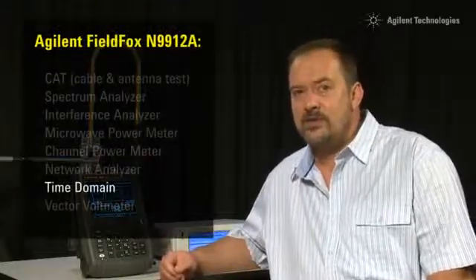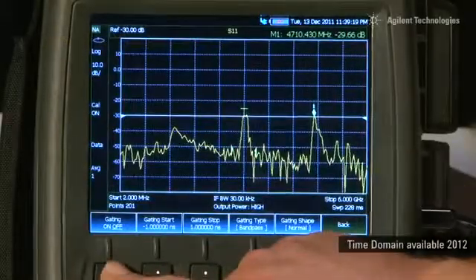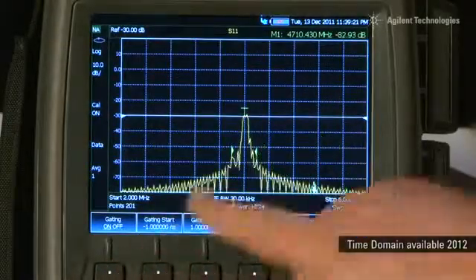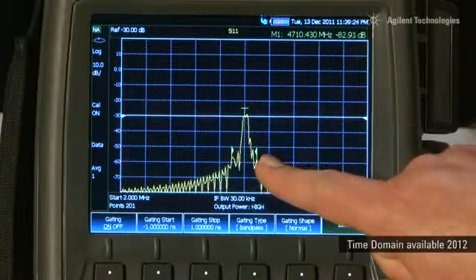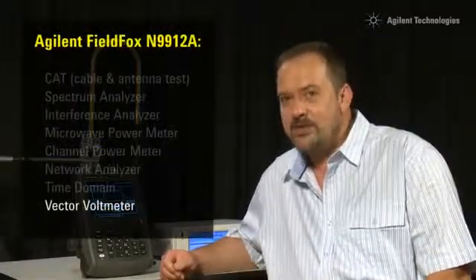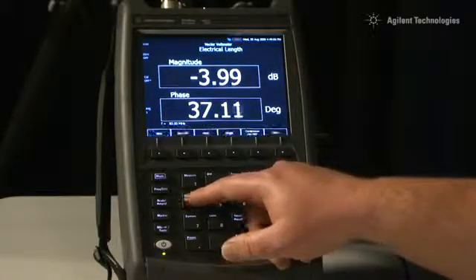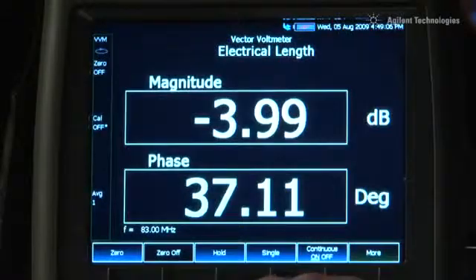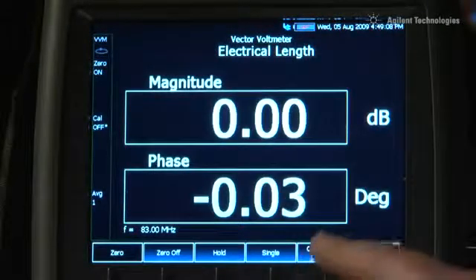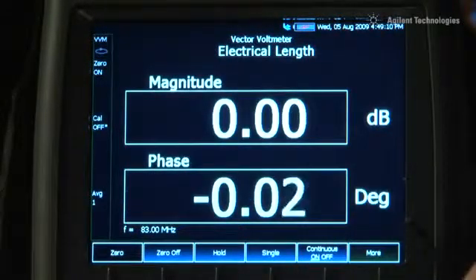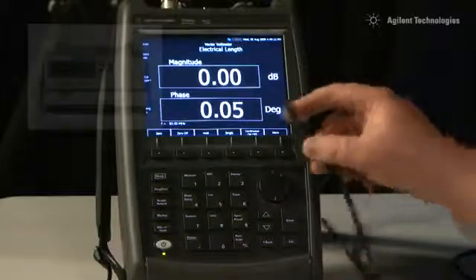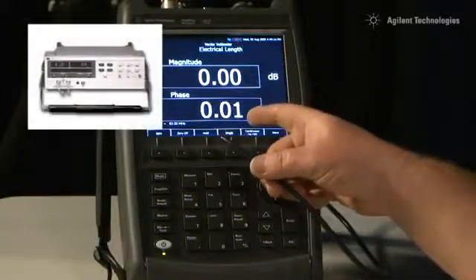And with the new time domain option, you can even make time domain measurements of these same devices, just like on a bench VNA. The vector voltmeter option lets us compare the electrical length of devices. For example, we can accurately phase-trim cables for radar and direction-finding systems, producing matched pairs with the same electrical length and phase delay, just like we did with the old HP8508A vector voltmeter.